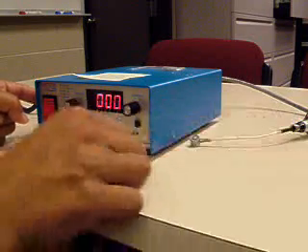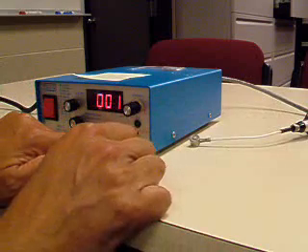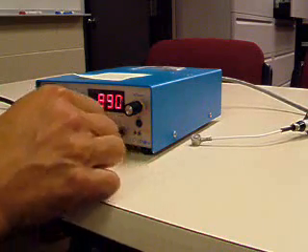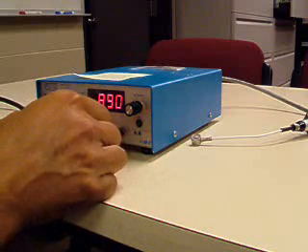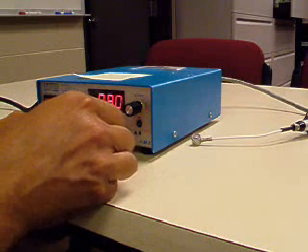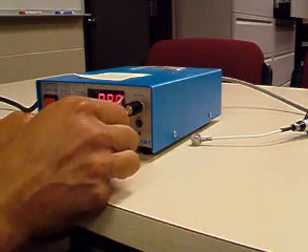First thing you do is set your zero until the display reads zero, then you press the cal button and dial the cal number in until this reads 890, which is actually 8,900 psi because there's a X10 down here. There's a zero that's not shown.